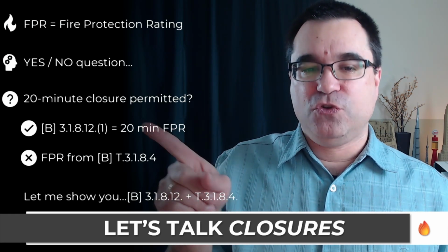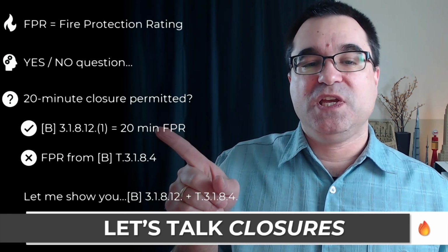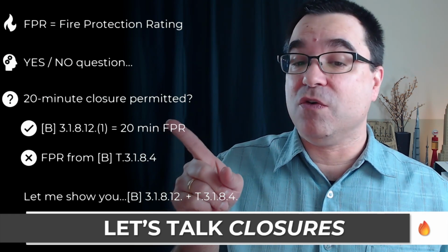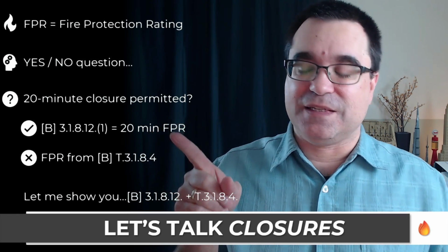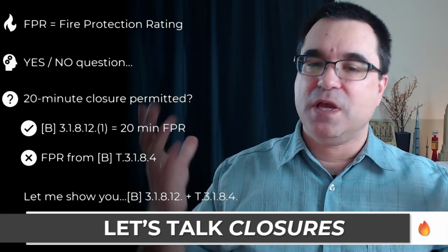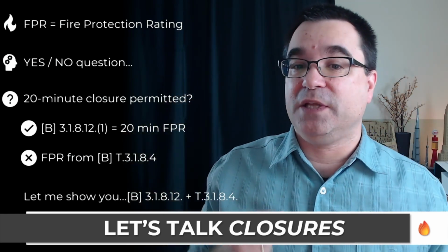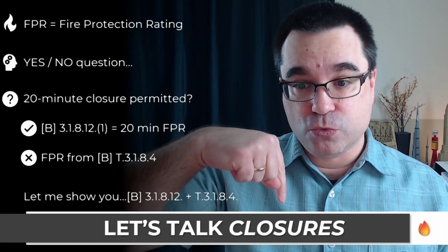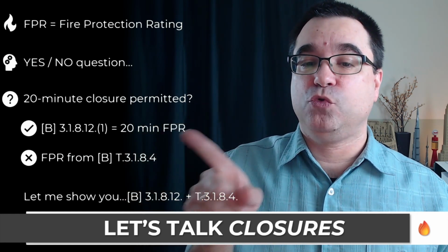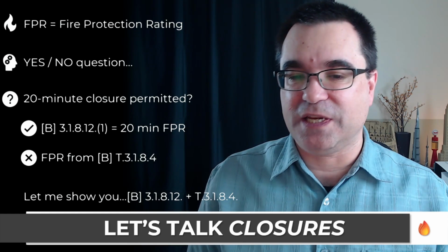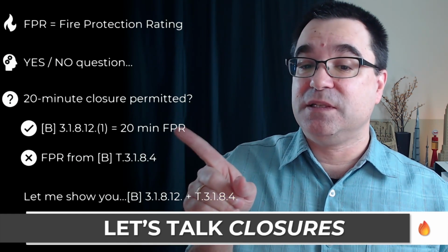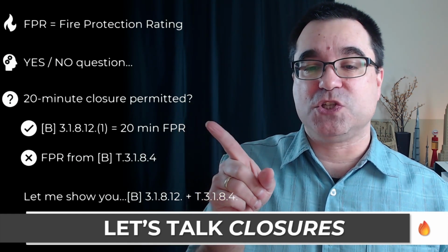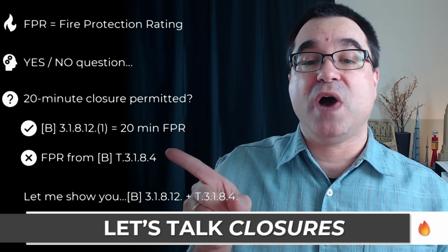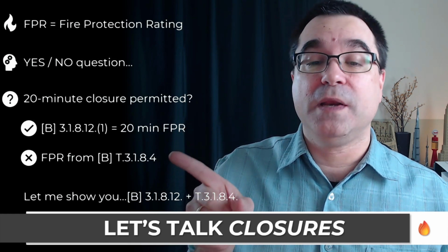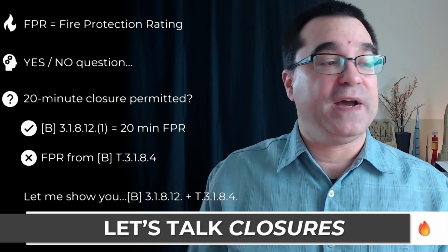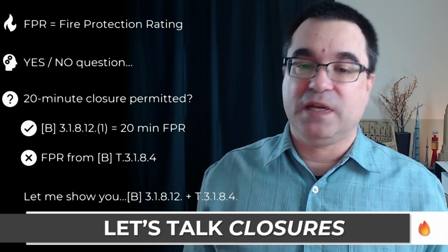So if you go to sentence 3.1.8.12.1, under that sentence, all the clauses under there will give you the guideline to evaluate whether or not that closure is allowed to be a 20-minute fire protection rating. If none of these conditions apply, so if the answer is not yes, then you have to go to table 3.1.8.4 to find the fire protection rating of that assembly.